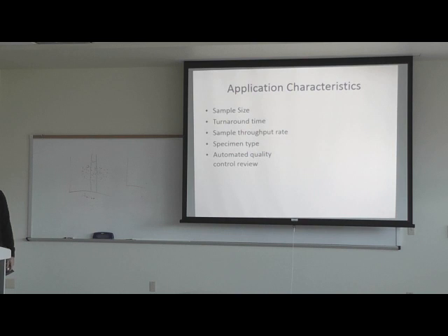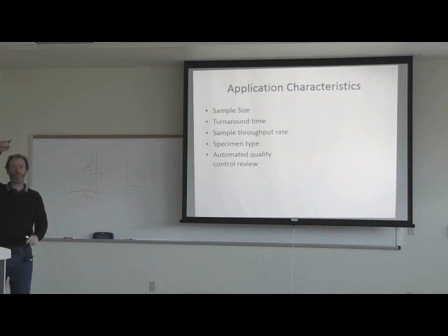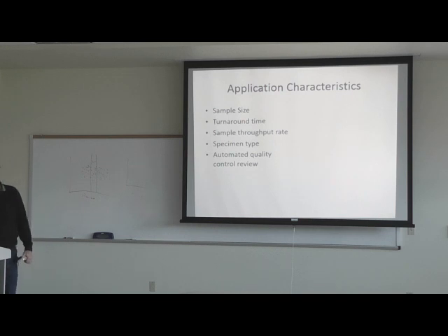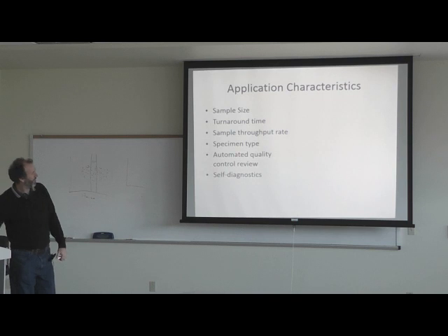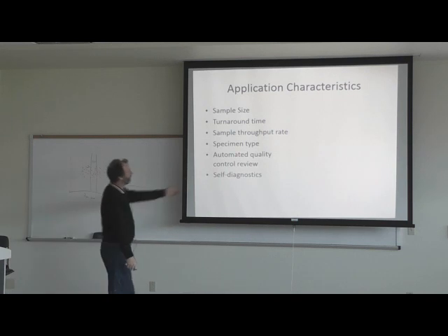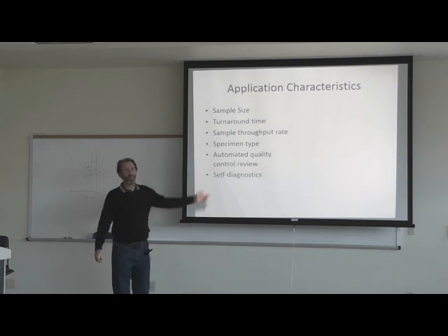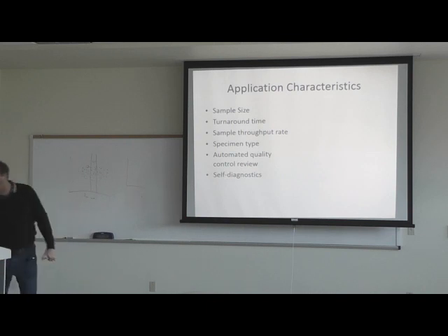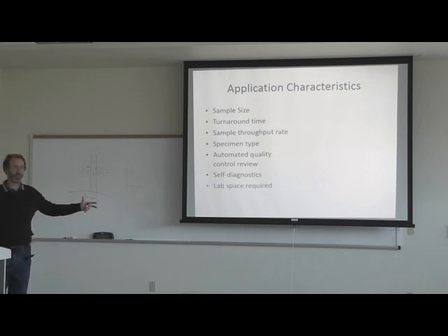The R-4S rule means your precision has gone way bad all of a sudden. There are also self-diagnostics on some machines, which help you out. Lab space is important — a lot of hospitals have limited space for their lab, and some of these automated machines take up an entire room.